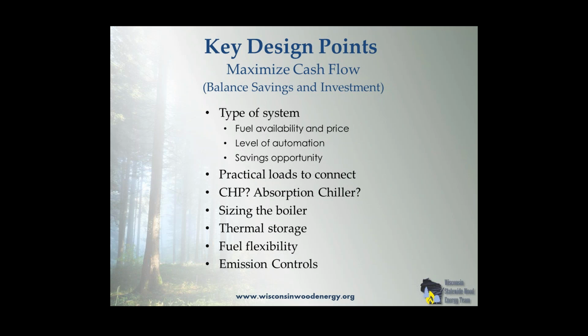And I can't stress this enough. Two items on here: thermal storage and fuel flexibility. Thermal storage, if you get down and try to pencil everything out, it's hard to capture what happens here, but biomass systems, especially wood chip systems, are not as responsive as fossil fuel systems, not nearly as responsive. And once you've got all this thermal mass inside that boiler or inside that firebox, you can't shut it down as easily as you could a conventional system where you're just injecting fuel into the system. So that thermal storage is really critical to making this thing responsive to the owner. It's really responsive to the load.